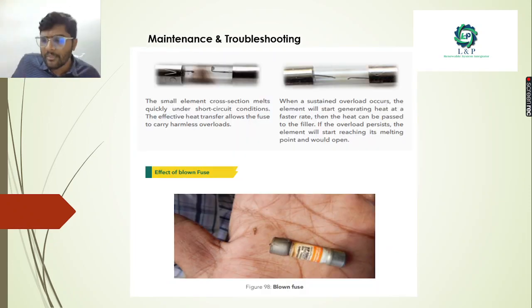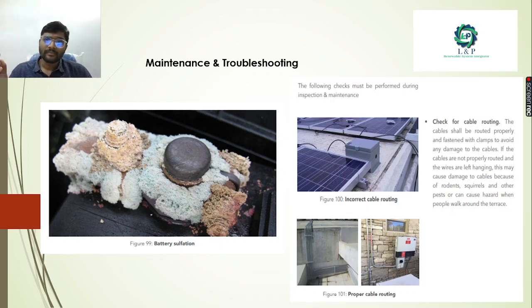The next important thing is that there is a possibility for the fuse to blow inside the direct current distribution boxes. Even on the AC side, in the SPDs, there is a possibility for the fuse to blow. So always make sure the fuses are correct, because if there is any short circuit or overload, the fuse can blow. This is how a blown fuse looks.